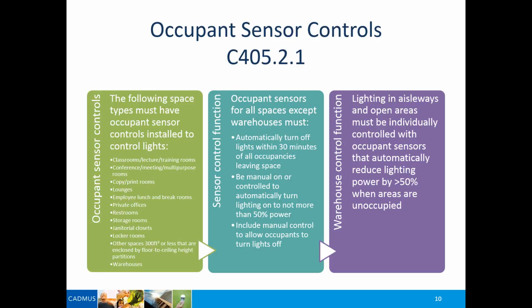From a warehouse standpoint, occupancy sensors are required in warehouses, and you can see the sensor control function in the center box here, if you will. Actually, I guess the right-hand box talks about the warehouse control function. When you're installing occupancy sensors to comply with the right-hand box, there are some requirements. For one thing, the lights must be turned off automatically after 30 minutes of occupants leaving the space.